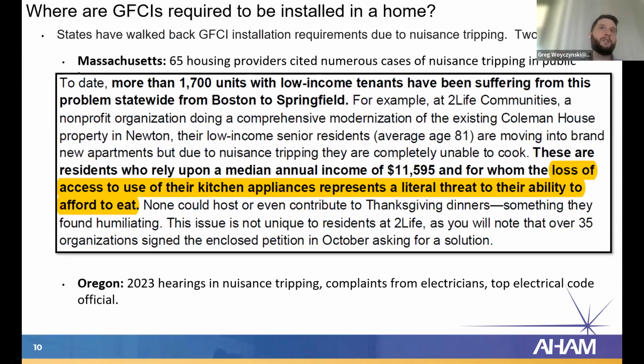There are states that have walked back GFCI installation requirements due to nuisance tripping. And we'll get into exactly what nuisance tripping means on the next slide. Massachusetts is a great example. 1,000+ cases of nuisance tripping in a very short period of time in Massachusetts. So these are folks who did not have access to their kitchen appliances, did not have access to their air conditioning appliances, their ranges, their refrigerators would not turn on. Safe, brand new appliances would not turn on because the GFCI kept tripping. So Massachusetts has acted and has now changed their electrical code to say, if you are nuisance tripping, you can go ahead and take out the GFCI.